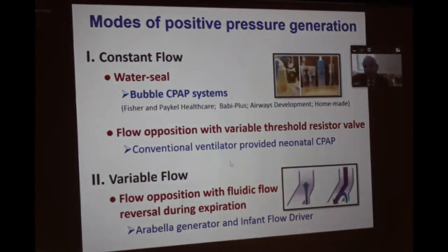So now that I've spoken about the interface, I'm going to briefly talk about how to generate the pressure. One can use a constant flow system, the simplest being a water seal system that utilizes the threshold resistor principle. The pressure is determined by the force applied to the surface area, and generated pressure is independent of the flow. Bubble CPAP systems such as Fisher-Paykel, Baby Plus, Airways Development, and homemade systems are most commonly used.